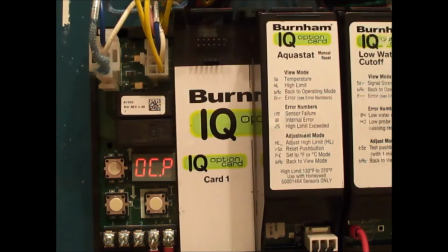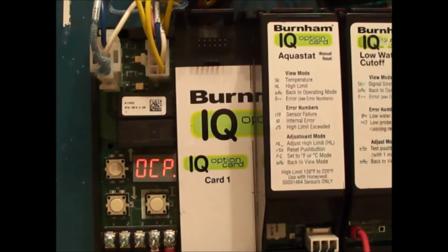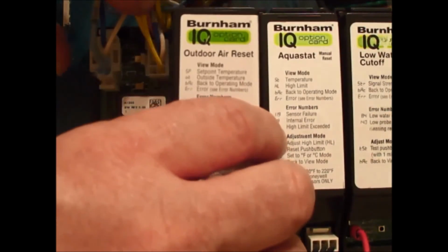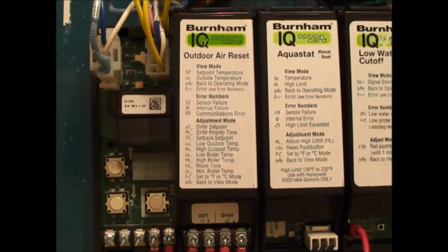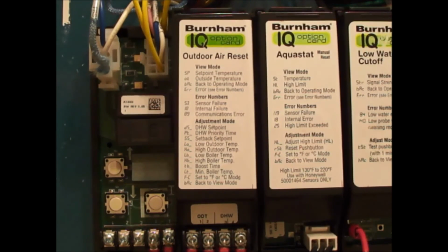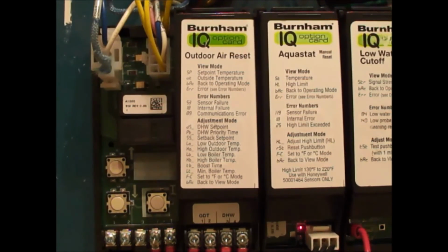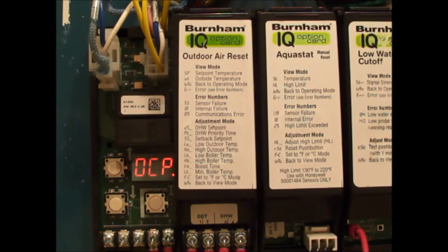When that happens, you have totally erased the card from memory, and the boiler will operate like the card was never installed. When you get the new card, of course, you would power down and plug in the new card, and wire up the wires. Take note, I lined up all 4 corners and slid it in. I did not put the bottom in first and then the top, as that has the possibility of bending over the pins. Then we would re-energize the system and the card would go back into memory. It goes back in within about a minute or less.